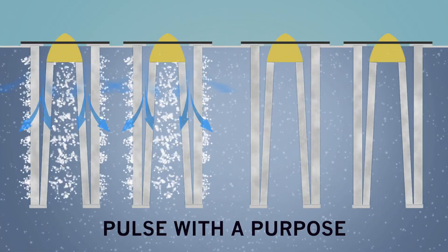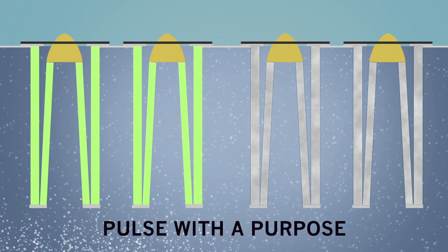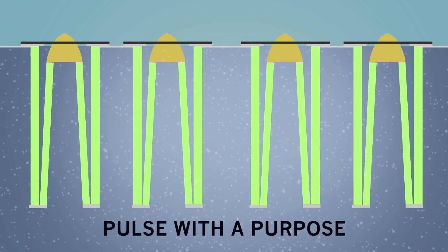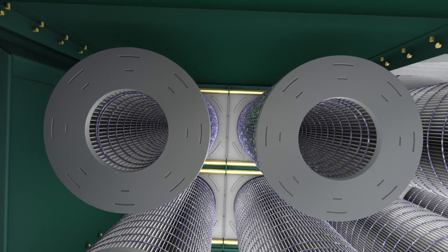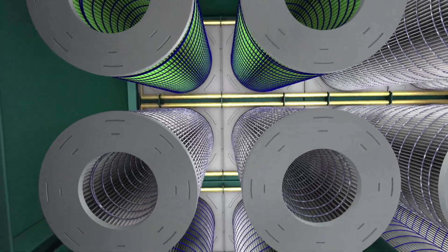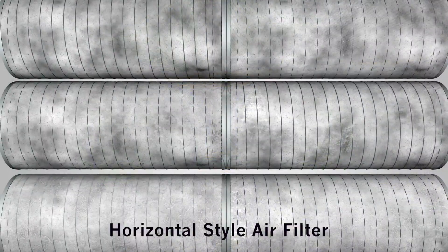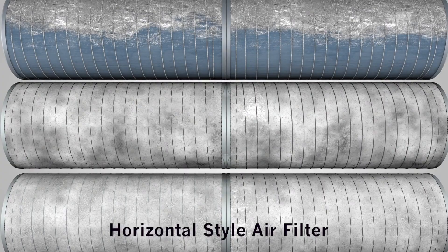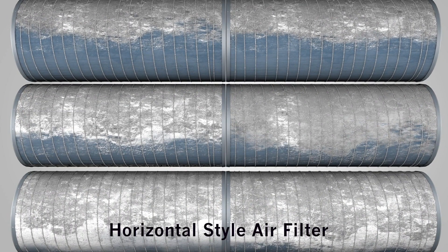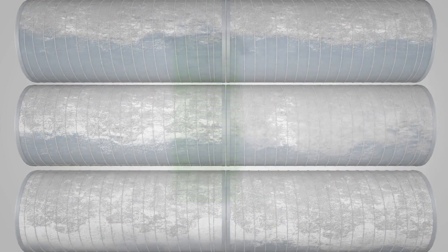With each pulse, the X-Flow filter cartridge ejects more dust out of the collector than any other filter and helps maintain a low pressure drop. In fact, up to 40% of each hemi-pleated cartridge is focused on discharging collected dust straight down to the hopper. This offers a huge advantage over horizontal-style filters that pulse 90% of the dust back onto adjacent filters and only 10% into the hopper.